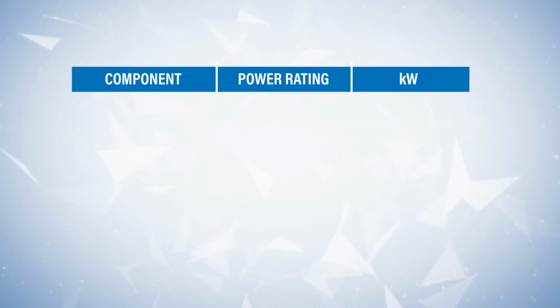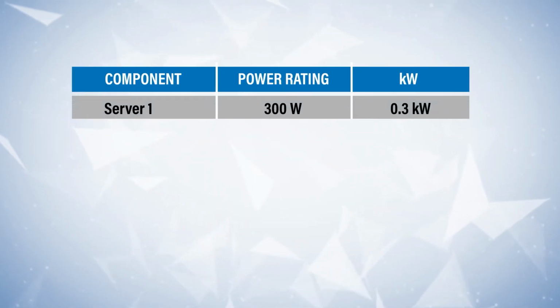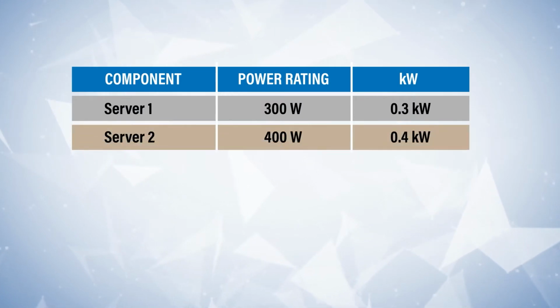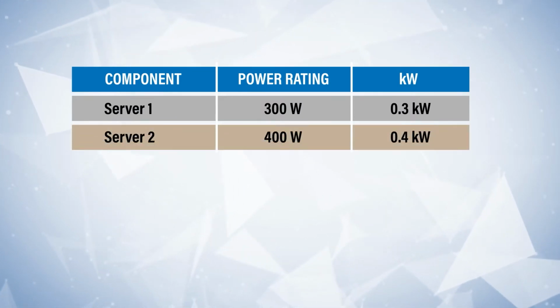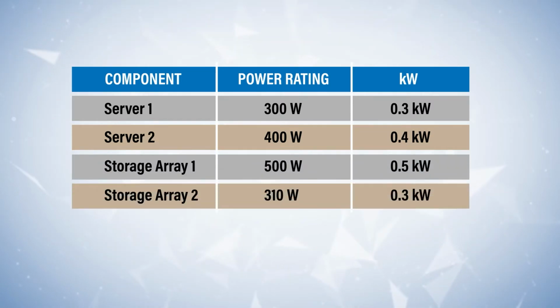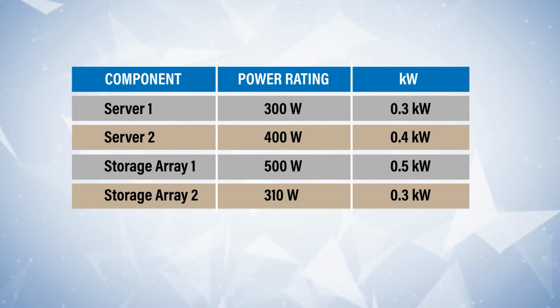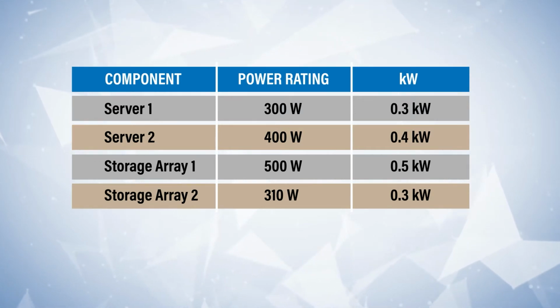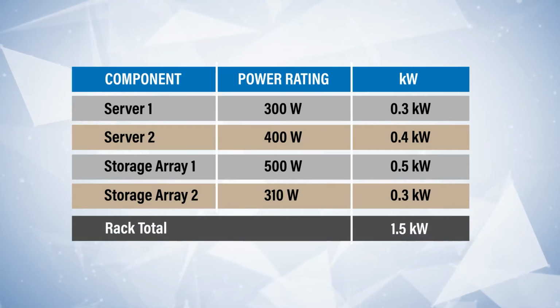Let us calculate the power now by putting this into a table, and we need to calculate this on a per rack basis, assuming that all the racks in the data center will be the same. Now for the example, we will take two servers with power ratings of 300 watts and 400 watts, which consume 0.3 kilowatt and 0.4 kilowatt respectively, and two storage arrays of 500 watts and 300 watts, with consumption of 0.5 kilowatt and 0.3 kilowatt respectively. When we sum up the total power, we get 1.5 kilowatts power consumption in a single rack.